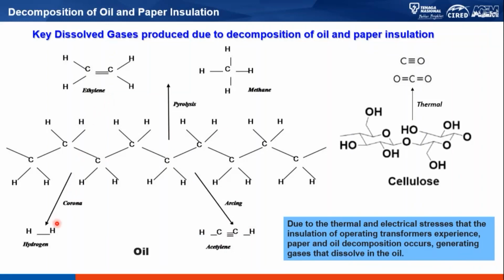All right, so that's on the oil. What about the cellulose or the paper insulation? When there is a thermal fault, the gases that can be produced are carbon dioxide, CO2, and of course carbon monoxide. So these are the gases produced as a result of paper and oil decomposition inside our transformer.